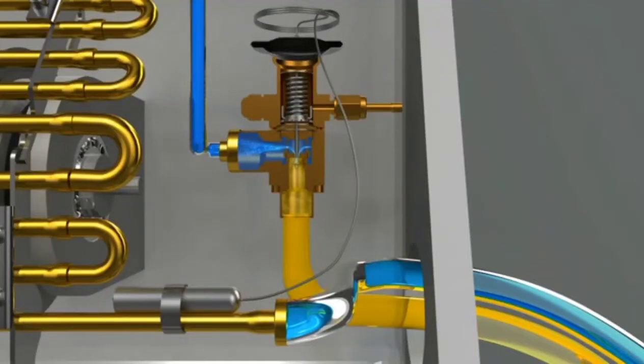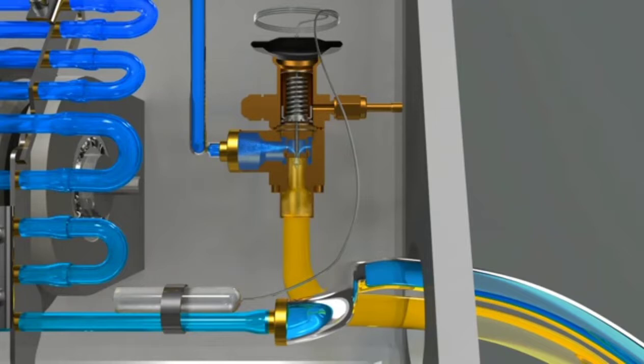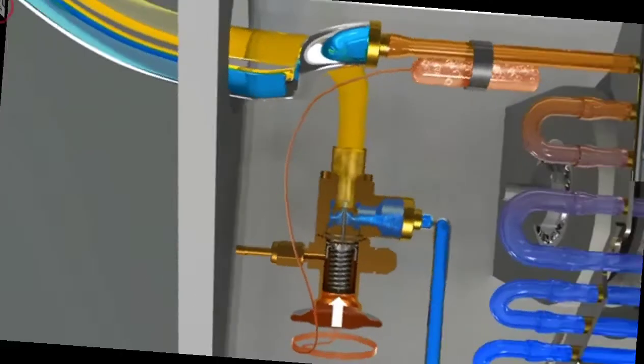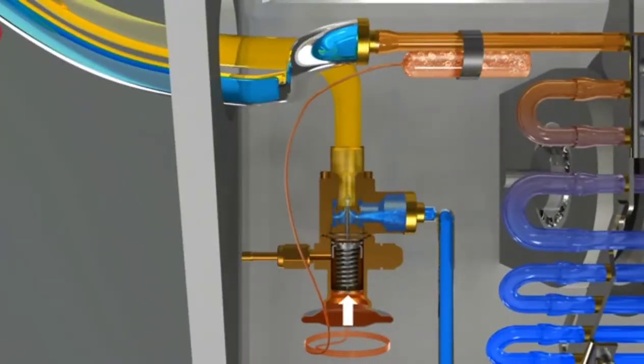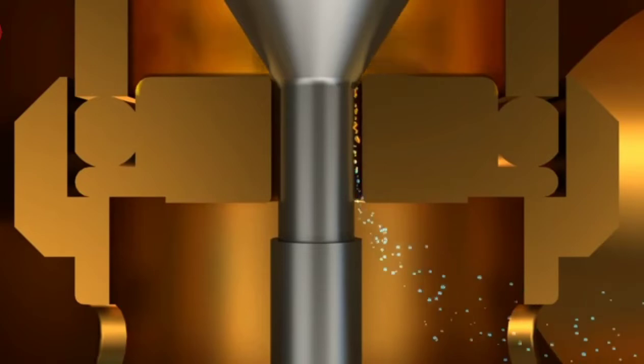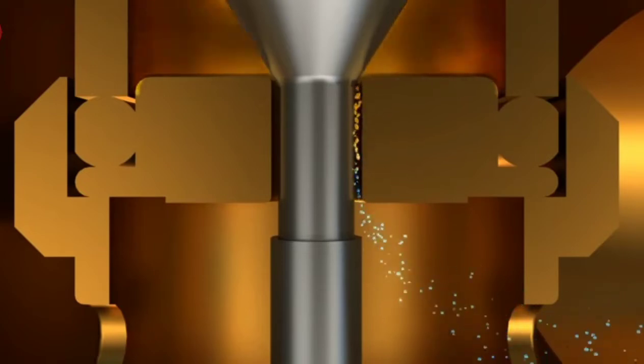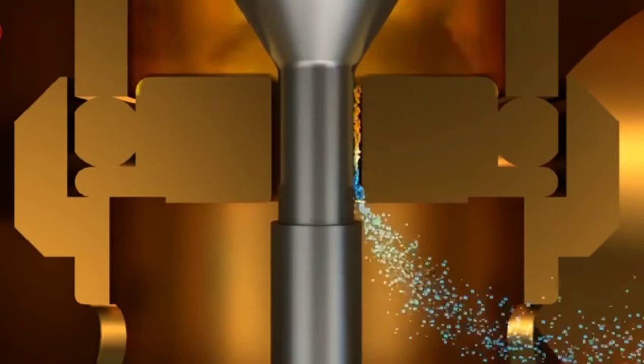The expansion valve is connected to a sensing bulb that detects heat. The sensing bulb is installed on the exit of an evaporator and detects temperature. Inside the storage is fluid sensitive to temperature changes, and as the temperature at the exit of an evaporator rises, the gas pressure rises, which in turn presses on a spring to send more refrigerant to the evaporator.